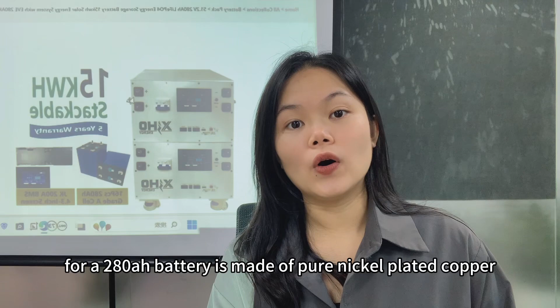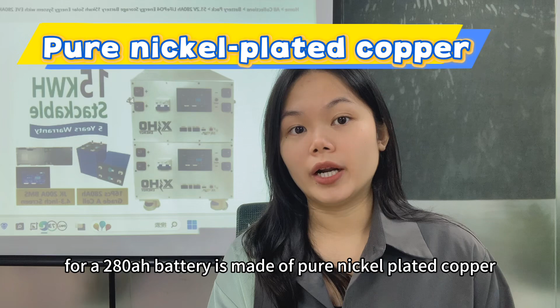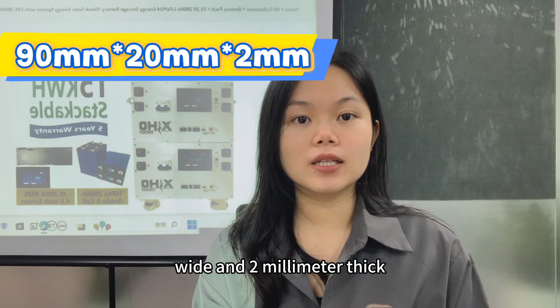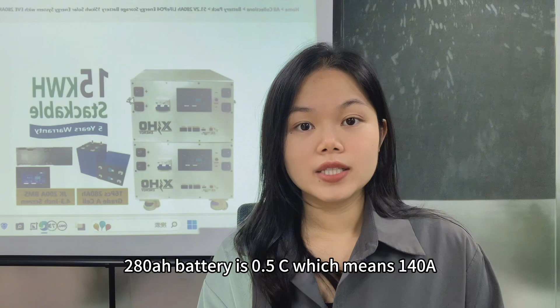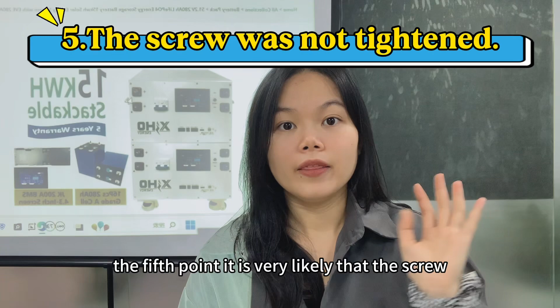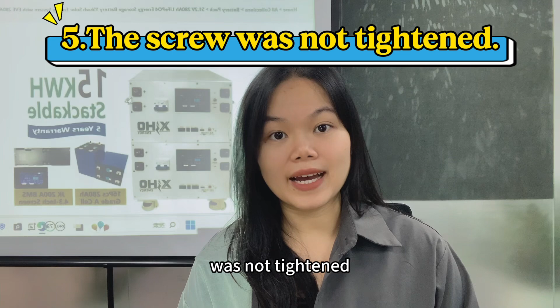For example, a standard connector for a 280 ampere-hour battery is made of pure nickel-plated copper and is 90 mm long, 20 mm wide, and 2 mm thick. It carries a current of 200 amp, and the discharge rate of a 280 ampere-hour battery is 0.5C, which means 140 amp.